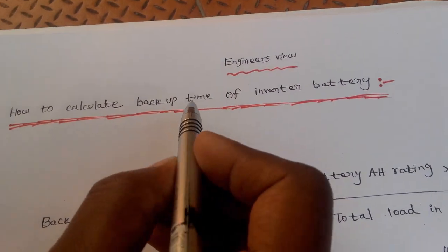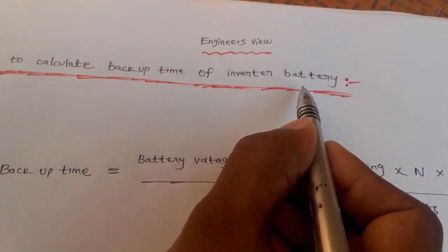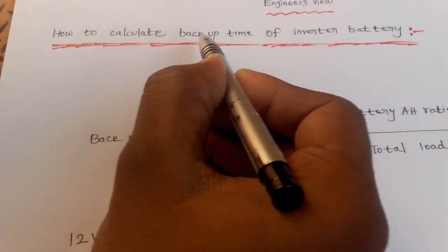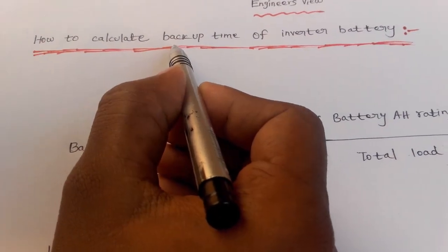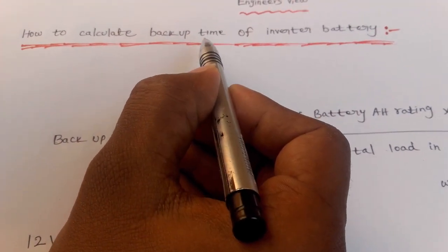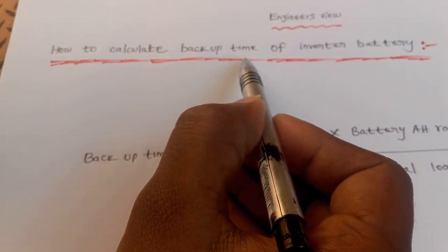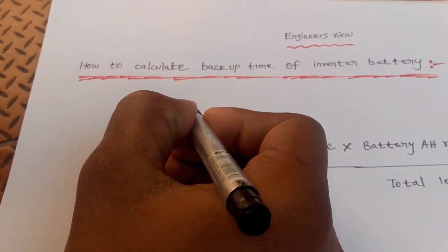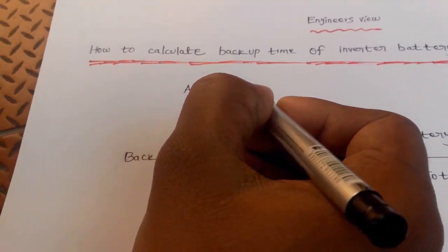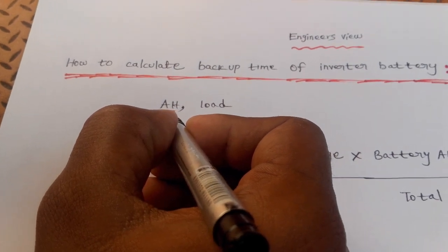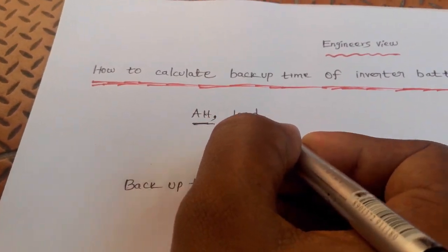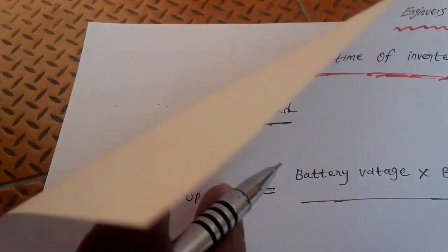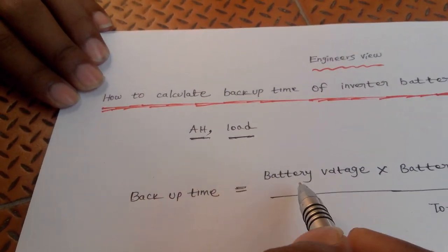How to calculate the battery backup time of inverter battery. The battery backup time general formula is: backup time equals battery voltage times battery AH rating times N times efficiency of battery divided by total load in watts.